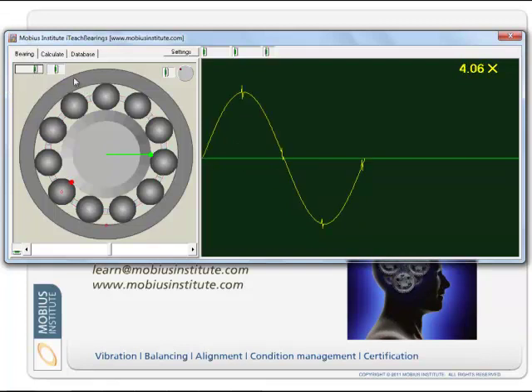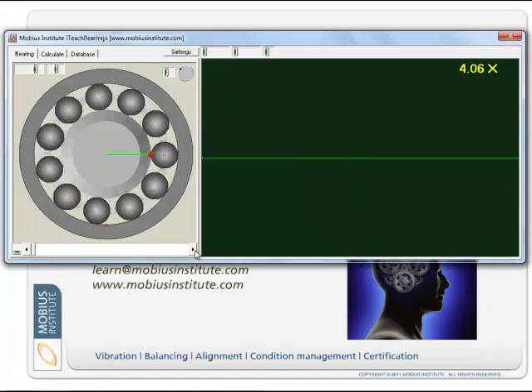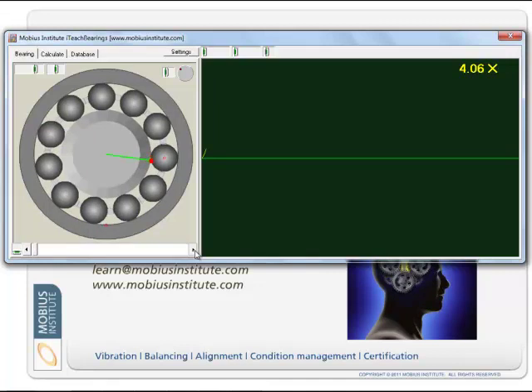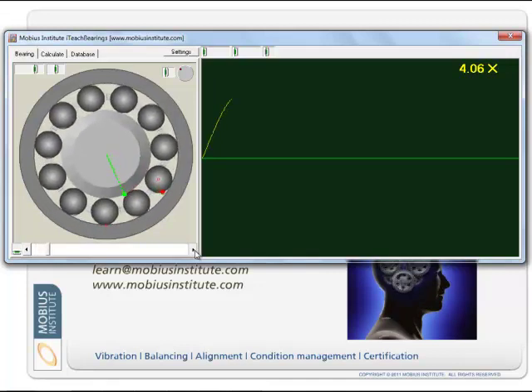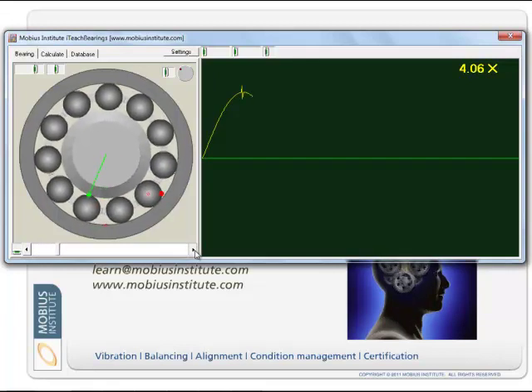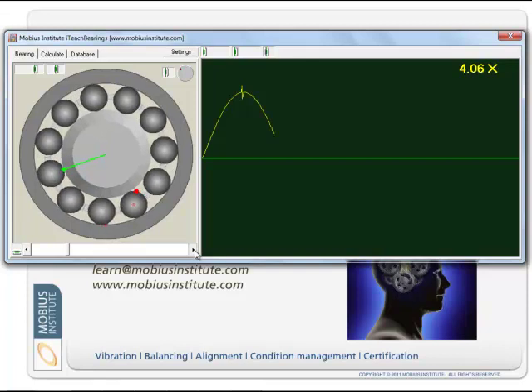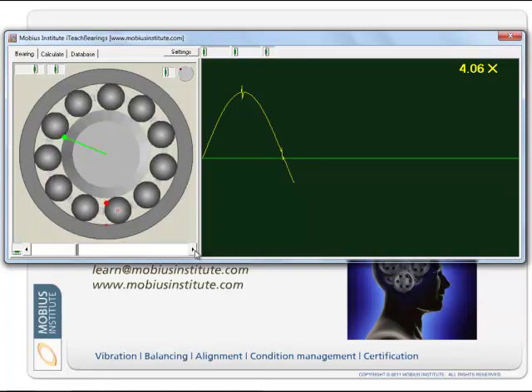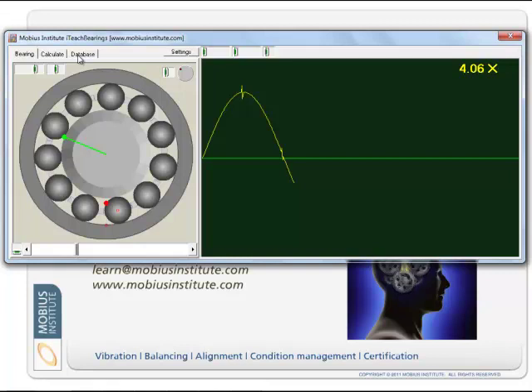For example, if we do a fault on the ball, we can see that as we rotate the shaft, we can demonstrate the case where the fault impacts just the inner race, just the outer race, or both. As we rotate the shaft, the rolling element or the ball or roller impacts there, and so on and so forth. We can just rotate the shaft and see what those defect frequencies will be — and they will always be non-synchronous. You can even enter different dimensions and go through a database to look at as many bearings as you like, but unless they're thrust bearings at particular angles, they will always be non-synchronous.